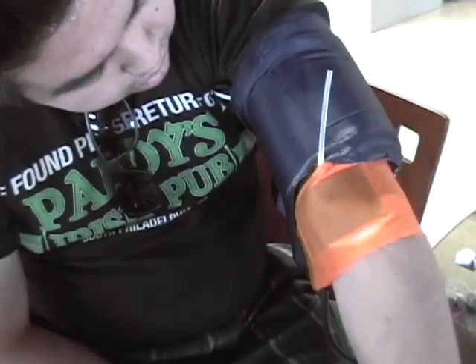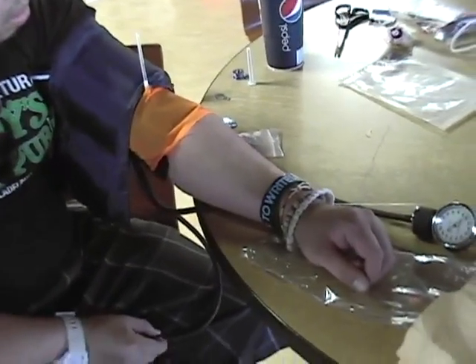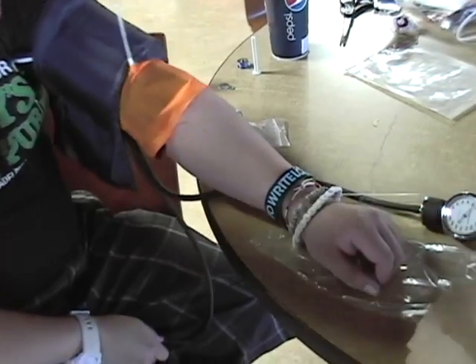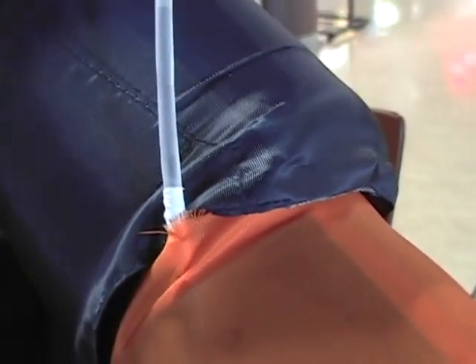Prior to inflating the sphygmomanometer cuff, the pulse of the patient should be seen, indicated by the periodic deflection in the water column. The cuff is then increased to a pressure of 180 millimeters of mercury. At this point, the pulsing in the water column should cease.